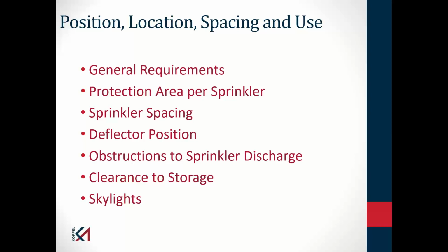Sprinkler spacing talks about how far the sprinkler may be away from the wall. And in most sprinkler types, there is a maximum distance and a minimum distance. There is also a minimum distance between most types of sprinklers. One of the things that I see sometimes is I'll walk through a building and see a sprinkler very close to a wall. Out of curiosity, I'll immediately go to the other side of the wall and see the sprinkler on the other side is some significant distance from the wall. They don't have to be equal distance, but it's a much longer distance.